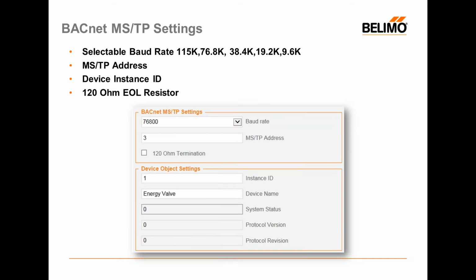As I mentioned earlier on in the presentation, the energy valve does not only have a web server in it, but it's also a BACnet application-specific controller that can communicate either via BACnet over MSTP or BACnet over IP, and it is a BACnet-listed device with BACnet Testing Laboratories. To address your energy valve for BACnet over MSTP, you do have to tie into the valve via TCP over IP like we spoke about in the first few slides.